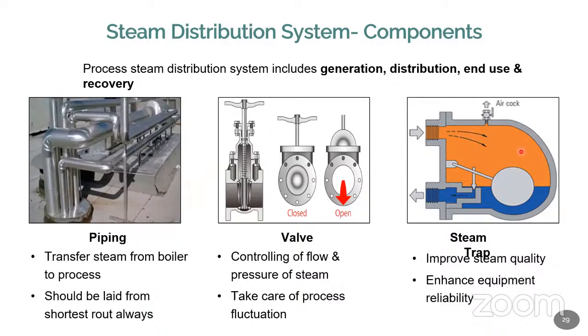And finally, we can have a steam trap. I told you the water droplets will always be available because of the condensation of the steam. So the water droplets will be properly collected by equipment called steam traps. When it is not collected properly, then what will happen? The quality of the steam will be affected. That is why the steam traps are located at regular intervals. Normally in an entire pipeline, based on the distance, the pressure, and the flow, the proper number of steam traps should be fitted to collect the water and let it out to the outside, or it will be connected to the condensate system.